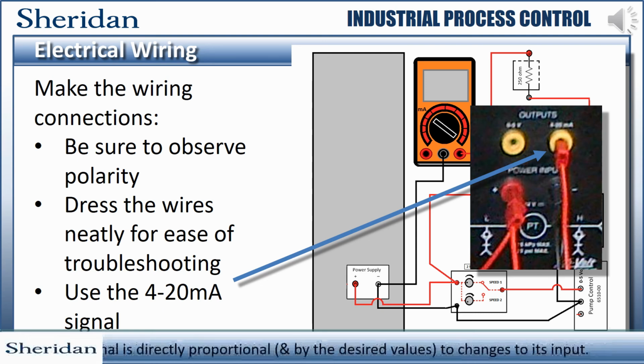The transmitters used at Sheridan can handle both 0 to 5 volts DC and 4 to 20 milliamps. For introduction instrumentation, you use the 0 to 5 volts DC. For this course, you'll be using the 4 to 20 milliamps. Keep this in mind as this will introduce a signal offset into your calculations.